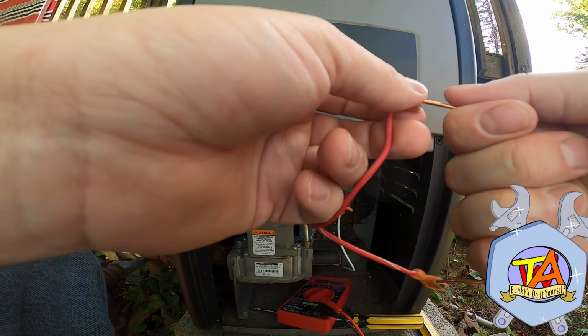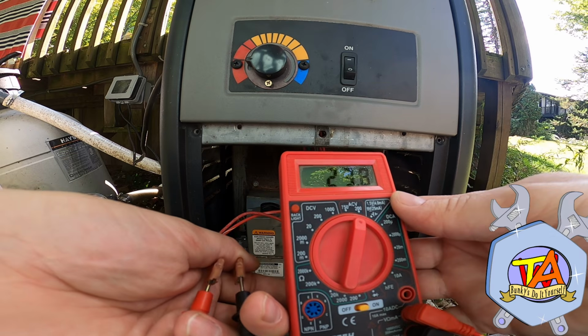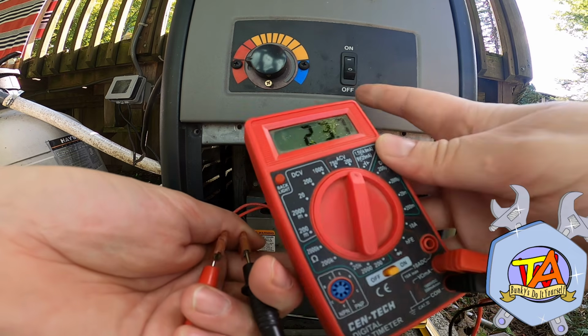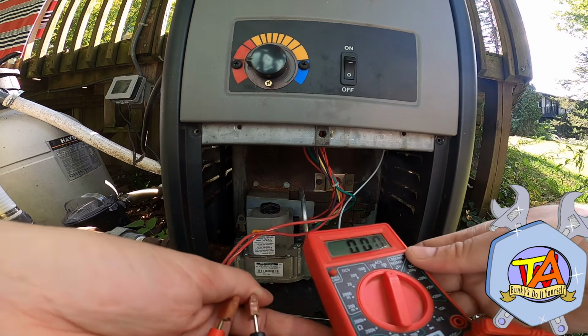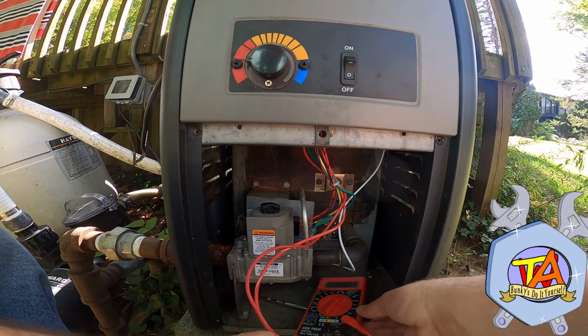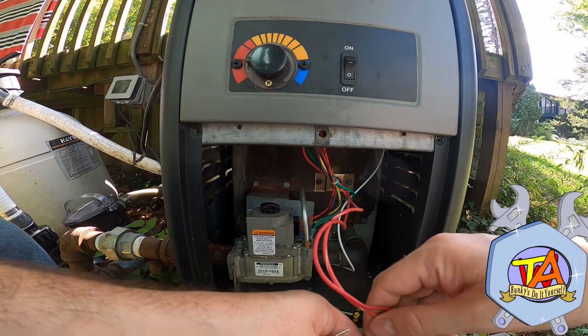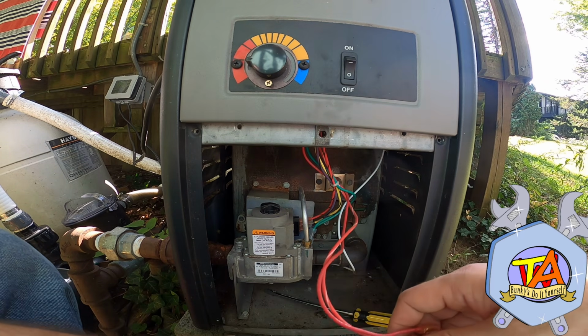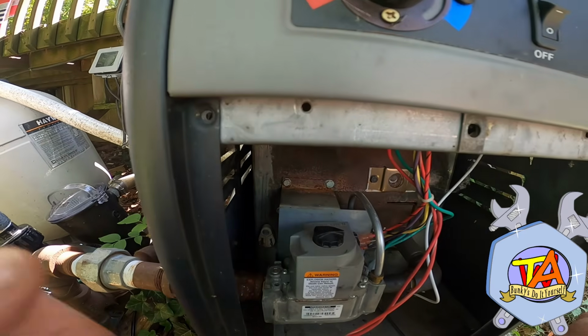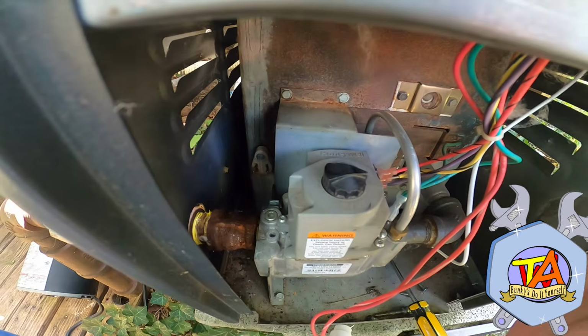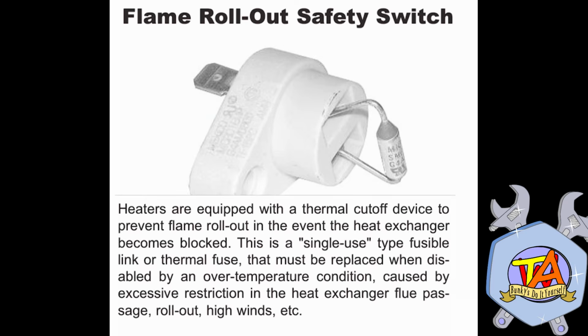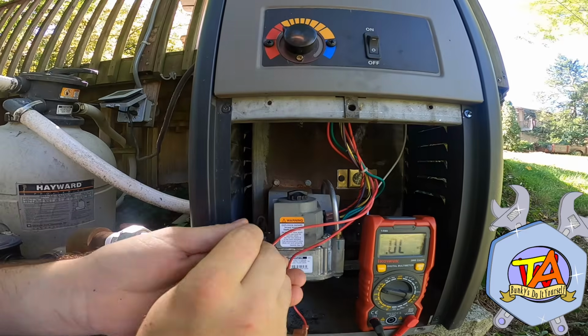After making sure to shut off the on switch, I can remove my bypass wire. And as you can see, with the switch on, we have 23 volts. This means that the fusible link had fused. Now this can be due to a couple of incidents. One is over temperature conditions. This is usually caused by excessive restriction in the heat exchange, high winds, etc.